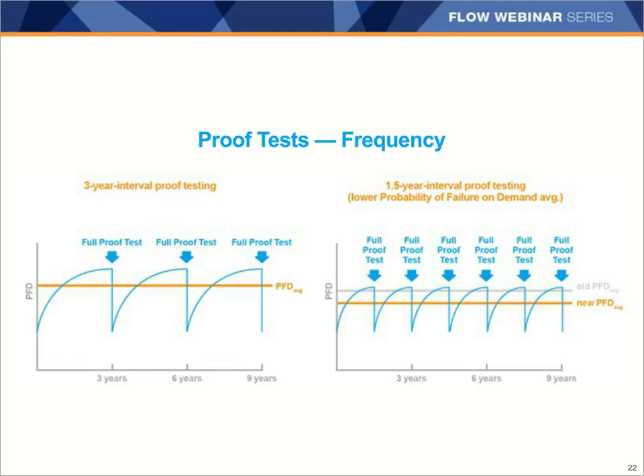If you choose to do a full proof test more often, like in the graph on the right, then you can reduce that probability of failure on demand and potentially get a higher SIL rating. This example shows that doing the full proof test every 1.5 years reduces the average probability of failure on demand. And I do want to make a note that these time intervals are examples only, and actual proof test intervals are going to vary depending on your SIS requirements and are going to be calculated depending on your SIL levels and other variables that you put in there.